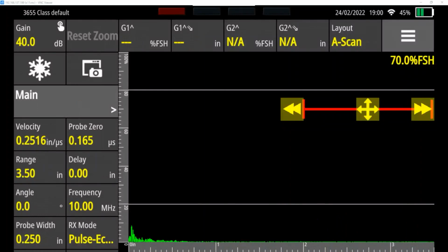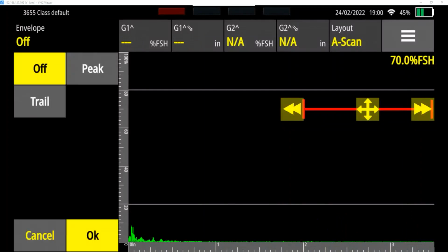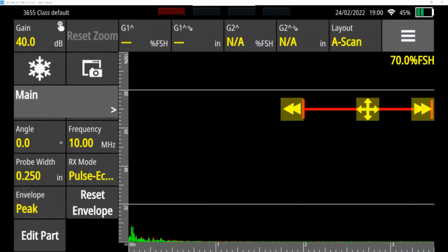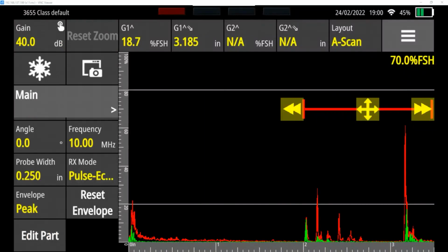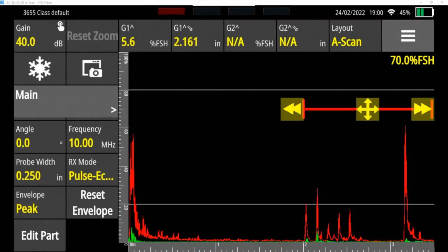So if I turn on my peak memory, here is my backwall, the overall width of the part. And here, some of these other ones are the different holes. I'm picking up a couple of them at a time because they're too close together to see. So you can see as I move this left and right, I can cause those different holes to show up. Those five or six echoes that are occurring between the 2 and 3 inch range.